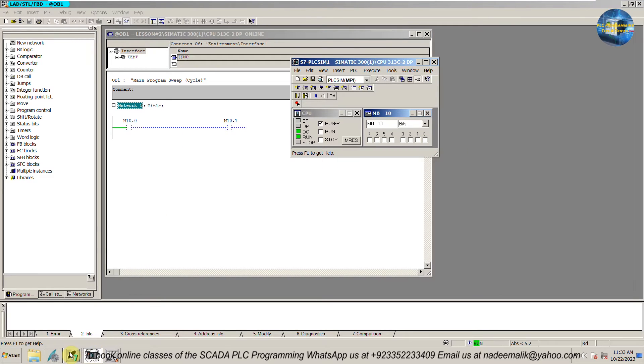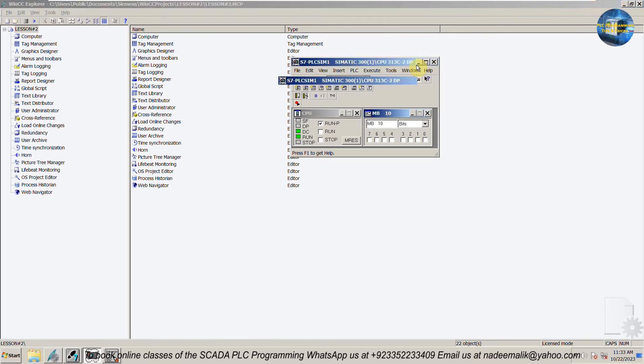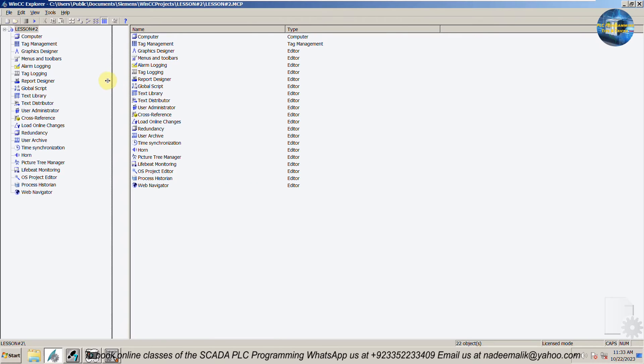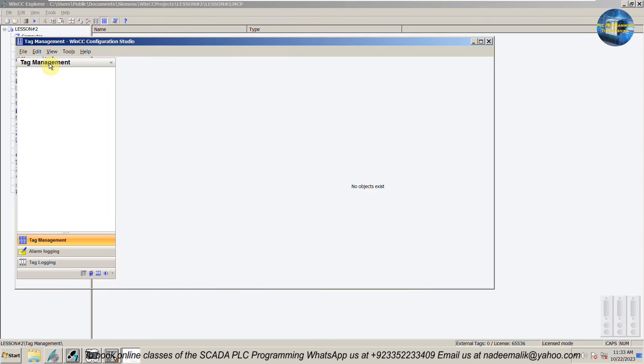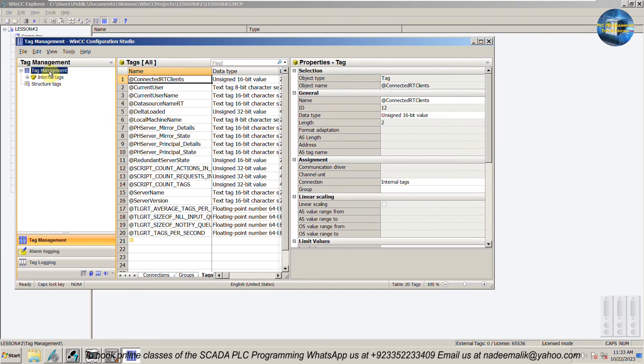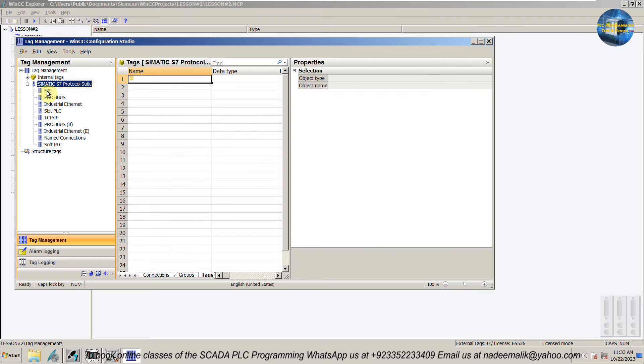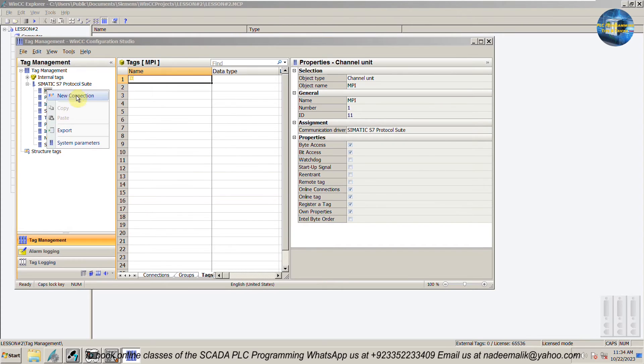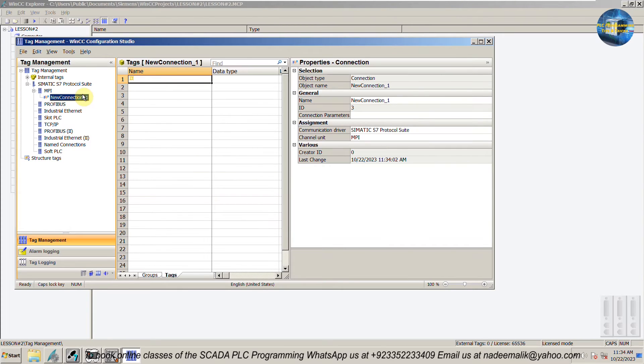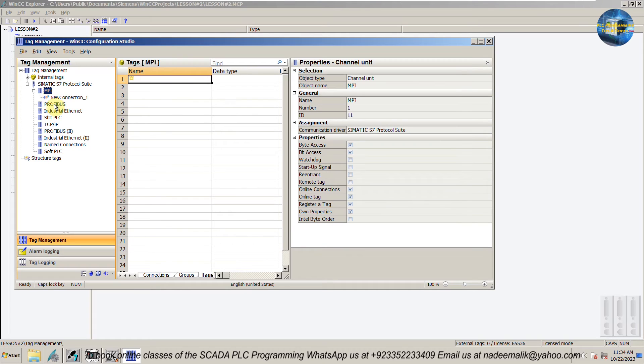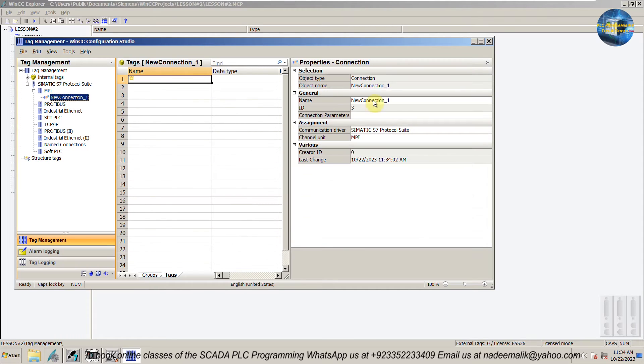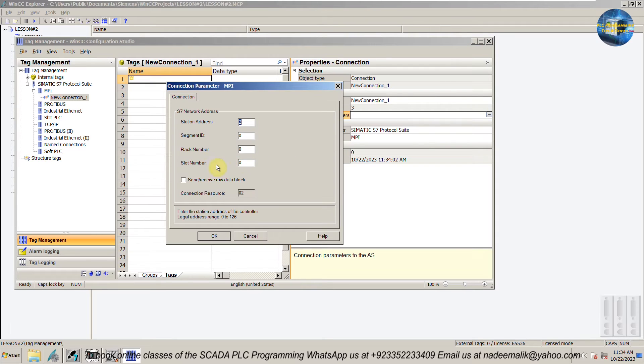Next we will open the WinCC Explorer software and double-click on the tag management. Here we have to add a new driver — Simatic S7 Protocol Suite. Next, right-click on the MPI and add a new connection. Then open the connection parameters and change the PLC slot number to 2, as our CPU in the project is at slot number 2 of the rack.